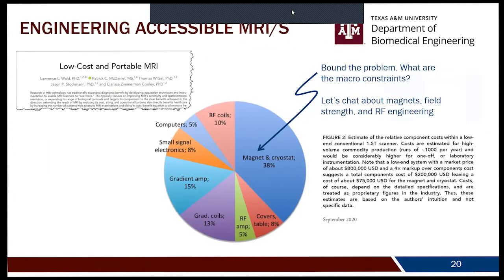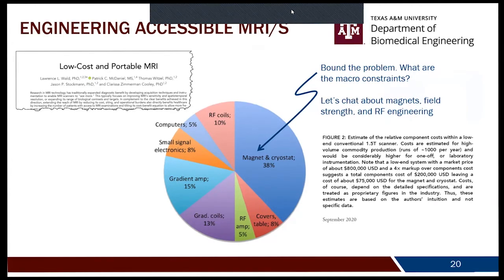As engineers, we're taught to bound problems. Looking at the cost of MRI, over a third sits in the magnet and cryostat. Today we'll talk about access to equipment and access to the power of MRI in the context of magnetic field strength — and how we as engineers can bridge what might be two competing concepts with respect to field strength.